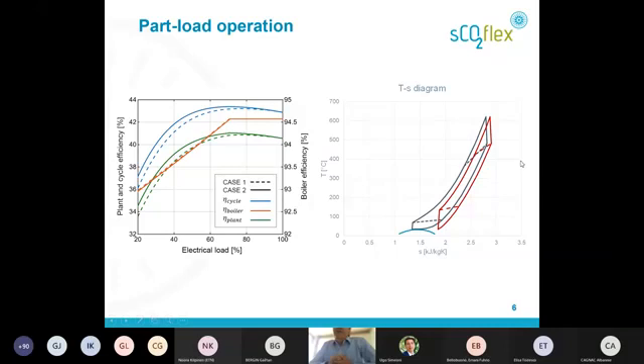About part load operation, I want to say something about this. We analyzed different operating strategies. The first one was to take the minimum pressure constant, the dotted lines. And the second one, that is the best operating strategy, is to change the minimum pressure in order to optimize it during part load, the continuous line.